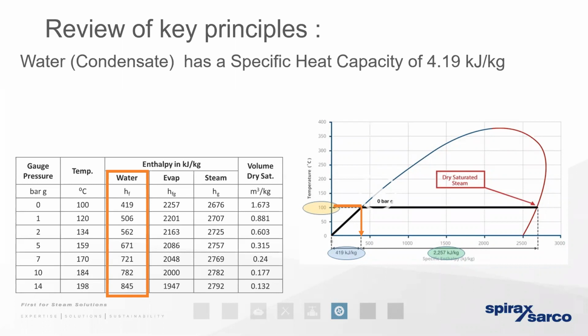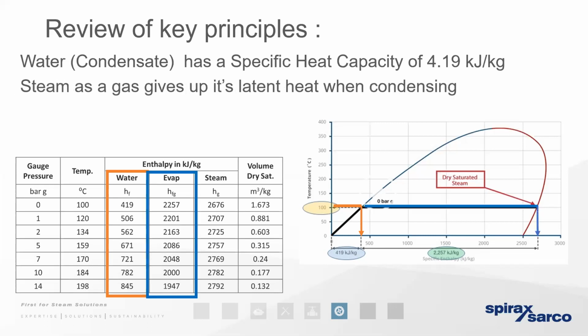So as we can see in the box in orange, the pressure and the temperature determine how much energy we need to put into the water to bring it up to boiling point. We refer to that as the sensible heat. Basically, it's how much energy we need to put into that water to get it to the point before it can change state to steam. And we know that that gives us boiling water, but we need to put further heat energy into that water to make it change state to a gas, to steam. We refer to that as the latent heat or the enthalpy of evaporation. And again, as you can see in the box that's highlighted in blue here, the amount of energy we need to put into that boiling water to make it evaporate will change in accordance with the pressure that we're generating and distributing that steam at.